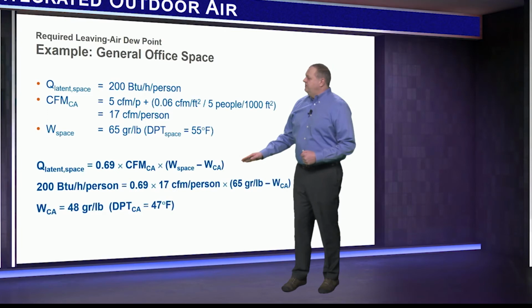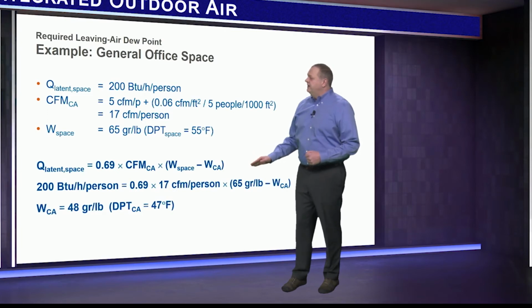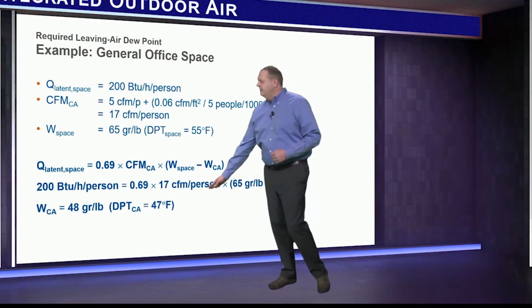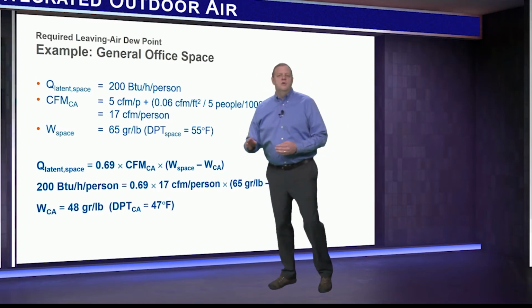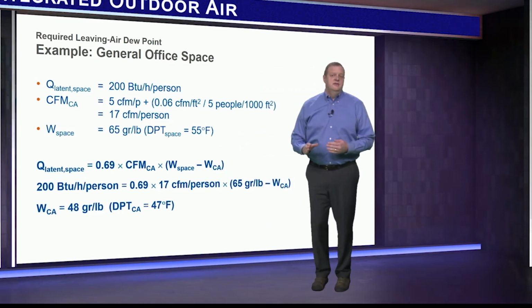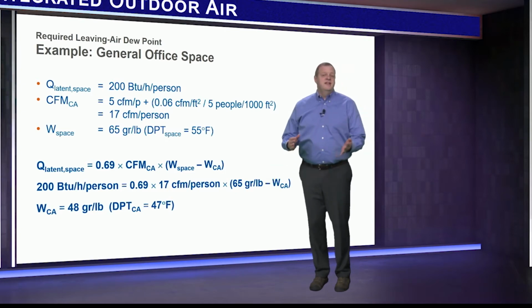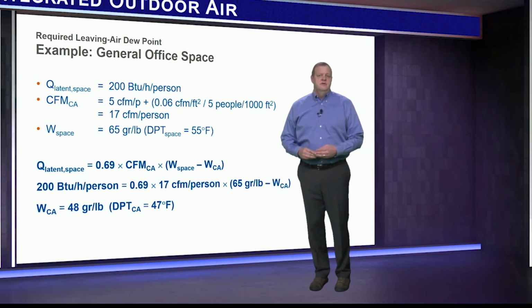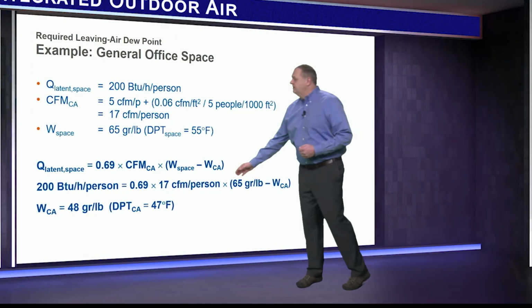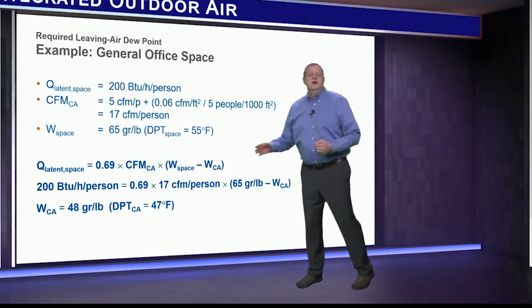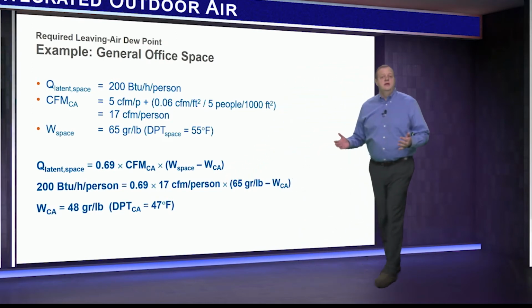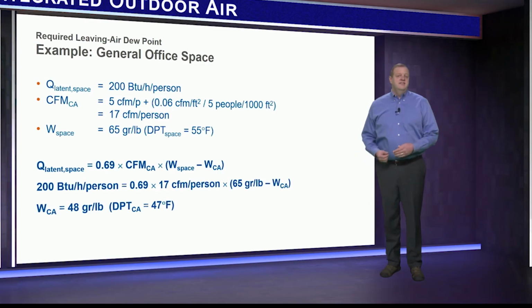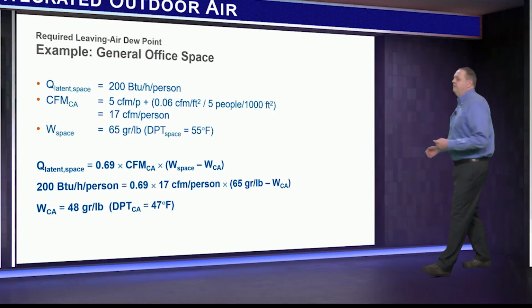Solving the latent heat equation here, this dedicated outdoor unit must dehumidify this quantity of air to 48 grains per pound in order to offset this space latent load. This equates to about 47-degree dew point. Of course, you could choose to increase this airflow, allowing for a higher leaving air dew point, but this would require the size of the dedicated outdoor unit and the ductwork to be larger.